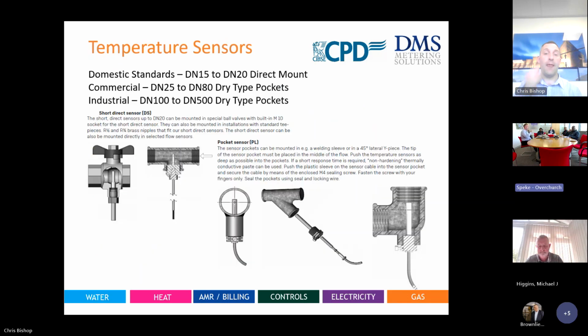And then temperature sensors. Yet again, it's not difficult, but there are still some contractors that cut corners. Temperature sensors must be mounted inside either T-pieces, if we're talking about domestics. You buy isolation T-piece valves that allow maintenance of the small domestic sensors themselves. Or a lot of customers, for anything 1 inch, maybe 40 millimeter and above, weld bushes into systems. The length of the bush determines how the pocket sits inside.